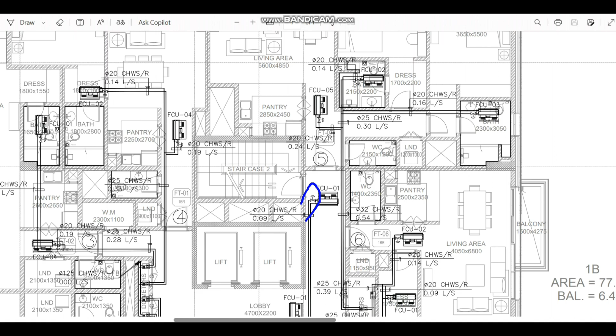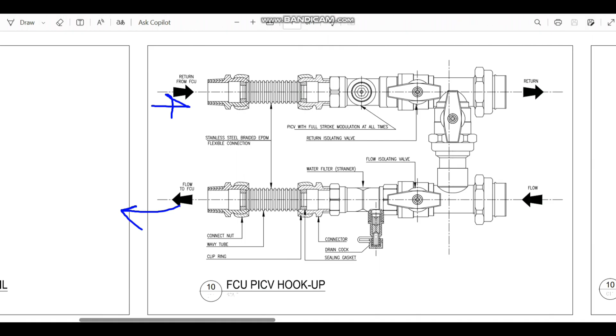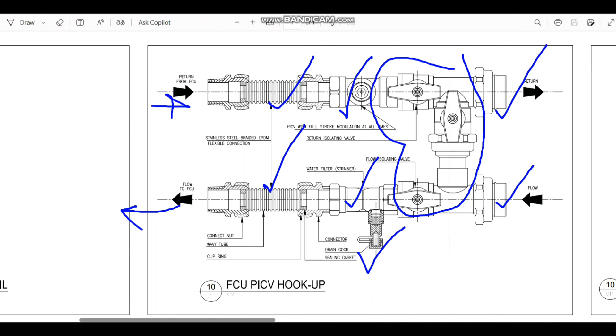And here the next one is, for example, here you can see we have the wall package. So that is called a PICV wall package. So normally we have the arrangement like this. For example, here you can see the supply to the FCU and this is the return from the FCU. So here we normally have union fittings. Then we have 3 isolation valves. Then here we have the drain connection, and here you can see the strainer, and here you can see the PICV valve, and finally we have the 2 flexible connectors. So this is called an FCU PICV hookup.